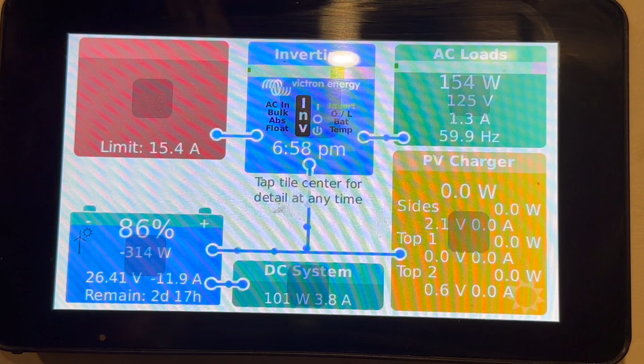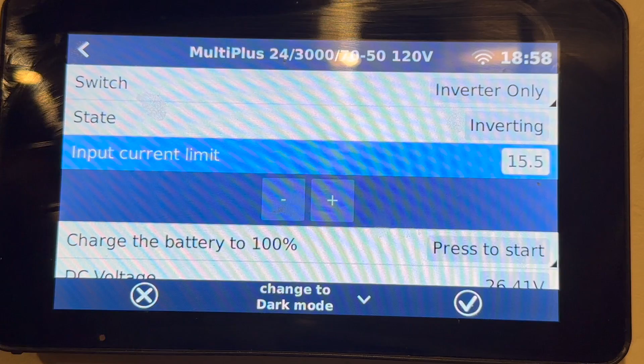Now, if you don't have GUI mods installed, what you're going to want to do is tap on the screen, go to Menu, MultiPlus, and then your input current limit. You're going to have to adjust that a little bit at a time for each individual input current source, and just make sure to knock it a couple of amps down from whatever the source actually is.